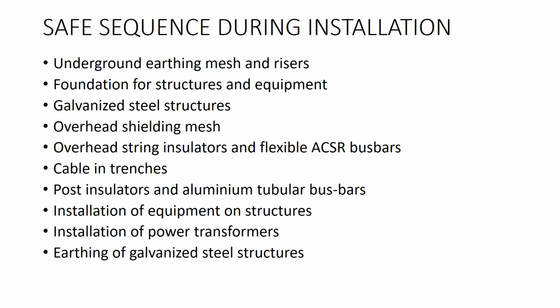After that, we can go for galvanized steel structures. After that, we can go for overhead shielding mesh, then overhead string insulator and flexible ACSR bus bar. ACSR means aluminum conductor steel reinforced. Then we have to go for cable in trenches, then post insulators and aluminum tubular bus bars. After that, we can go for installation of equipment on structures. After that, we can install the power transformer. Then the earthing of galvanized steel structures and transformer tanks and other plants to be earthed.